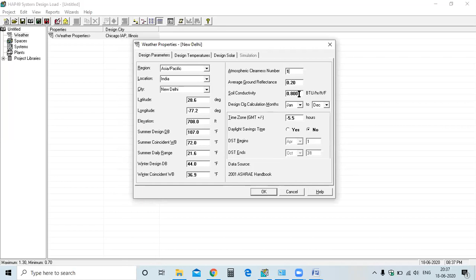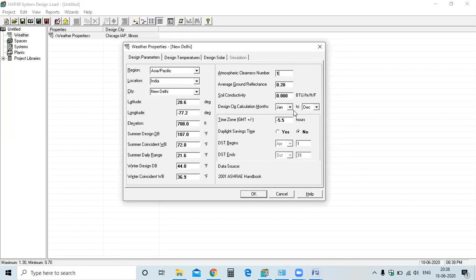Next is the design cooling calculation month. CLG stands for cooling. If you're only interested in the cooling part, select January to December, and it will automatically calculate for the peak month with the highest temperature. But if you want both heating and cooling load, you must specify the heating month, say March to October. The software will then design March to October for cooling, and the rest of the months for heating. So if you only want cooling, select January to December.